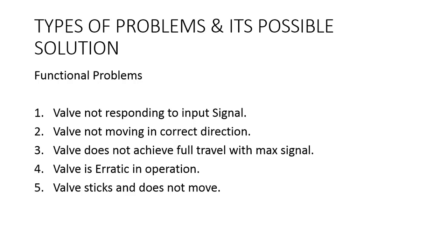First, when we say the actuator has insufficient travel, we need to check the valve datasheet and actuator nameplate. With these two, we will know whether the actuator has sufficient travel or not. If the positioner is not set properly, we can simply adjust the span setting and zero setting on the positioner. If the actuator is not connected to the valve properly, loosen the stem connector between the actuator and the valve stem and adjust the length of engagement of the valve stem.